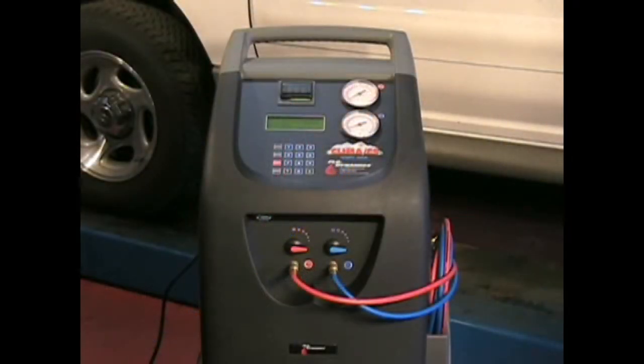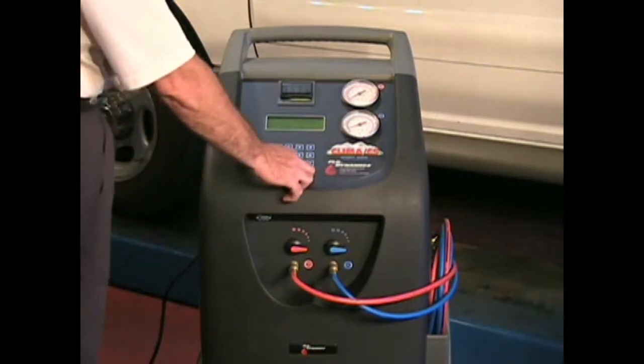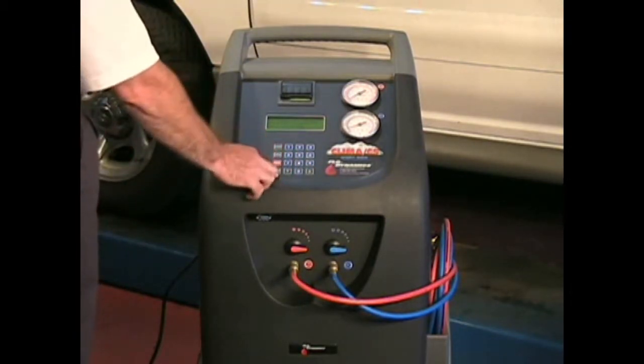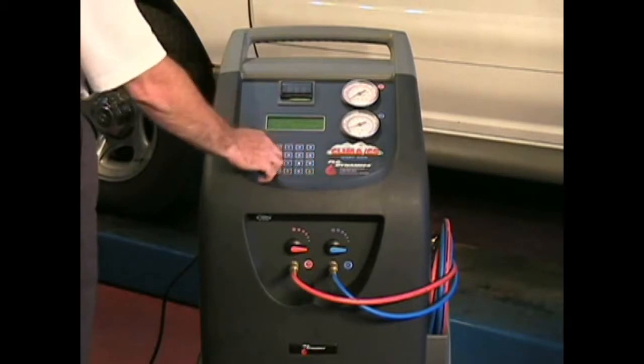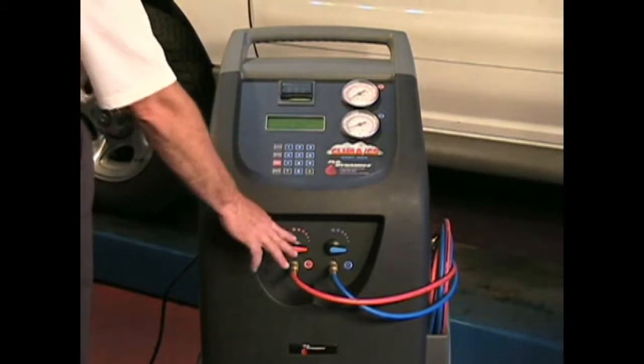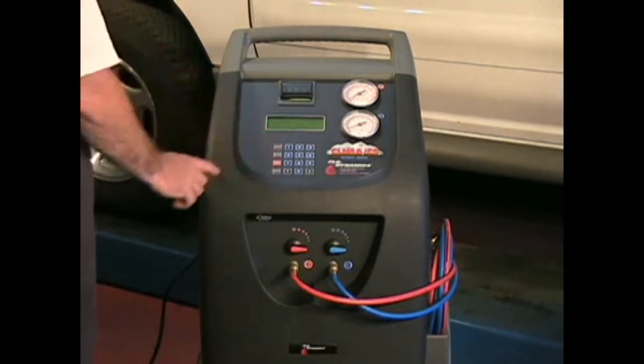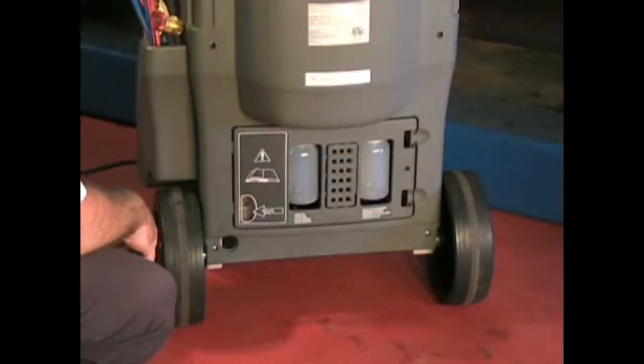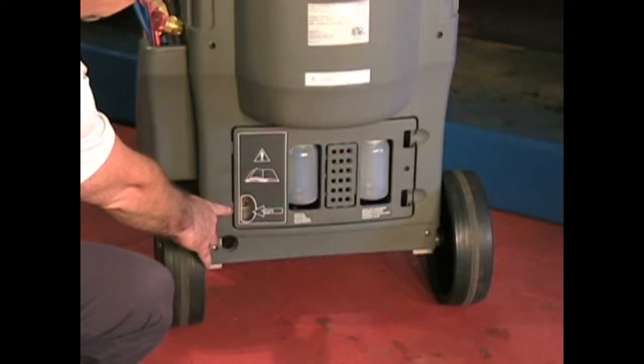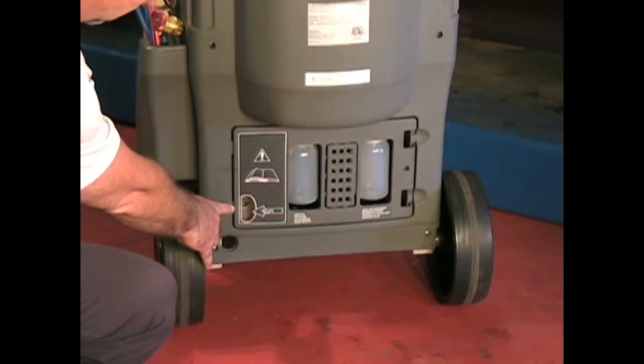The vacuum pump oil level can be checked by arrowing to Assisted Procedure, then Vacuum. The taps can be closed during this test. Press Start and observe the vacuum pump oil level. It should be at or just above the oil level line.